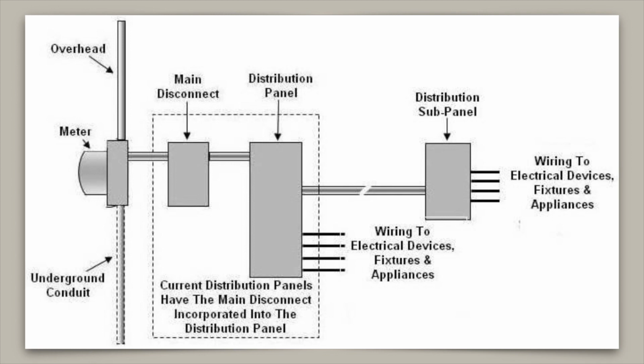The typical defect noted when inspecting subpanels is that the circuit coming to the subpanel is not from its own circuit breaker, but is from a double tap on the main lugs or main breaker. This is a safety hazard. Some of the typical defects are no main disconnect, double tap breaker, aluminum wiring, rust, and knob and tube wiring.